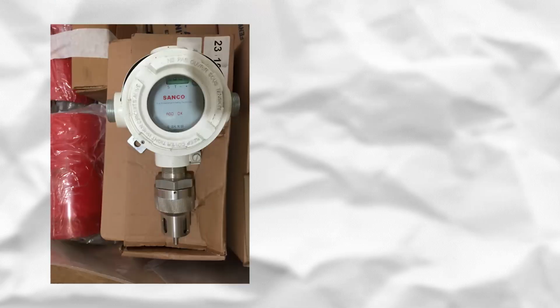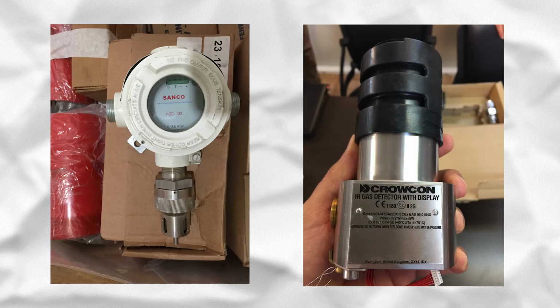Gas detectors are categorized into two subsets: catalytic and infrared type. Catalytic one is more applicable when the ambient temperature is higher than 60 degrees centigrade, like a gas turbine enclosure. Infrared type sensors have fast response time. On the other hand, they cannot be used in places where there is dust in the air. To install a gas detector, you need to know the composition of the gas. For instance, since methane is lighter than the air, CH4 gas detectors shall be installed on top elevation.